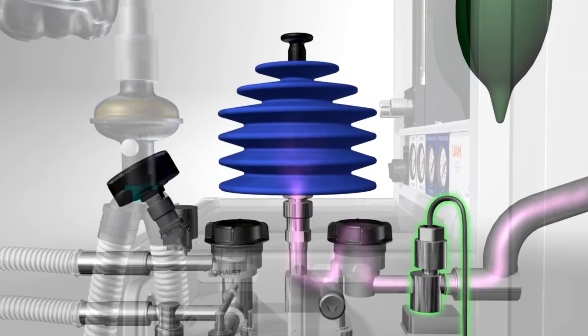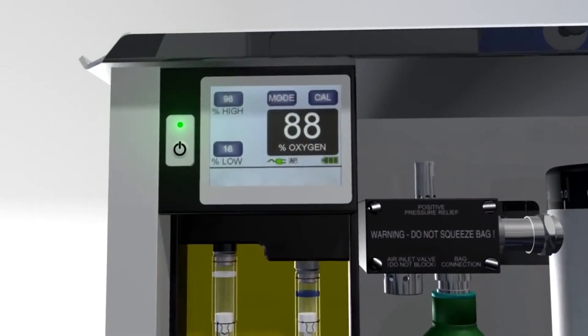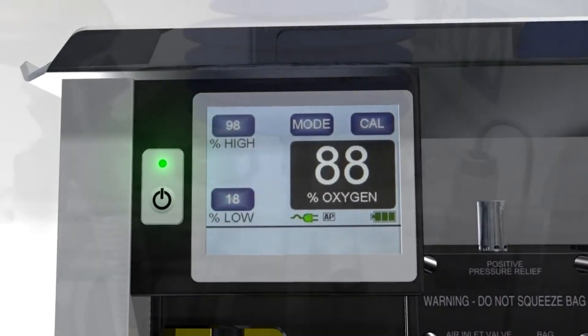The plenum vaporizer is an elegant device which works reliably, without external power, for many hundreds of hours of continuous use and requires very little maintenance.